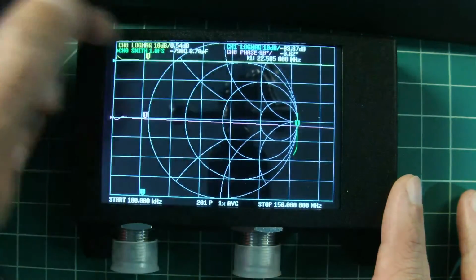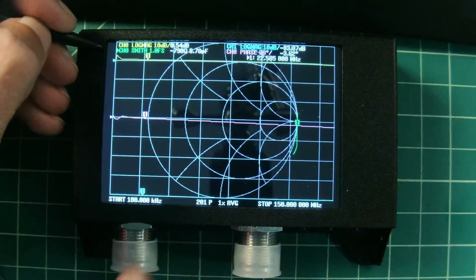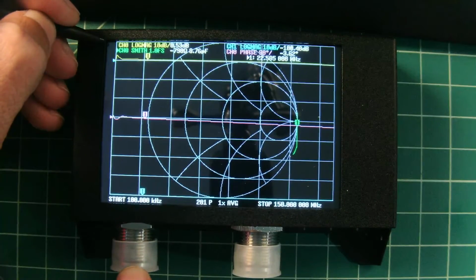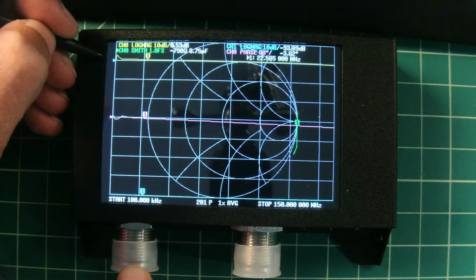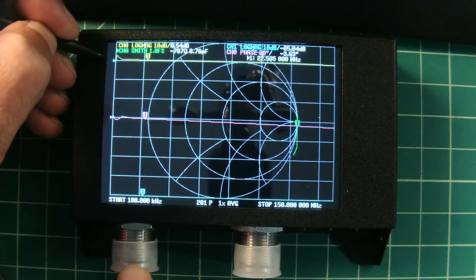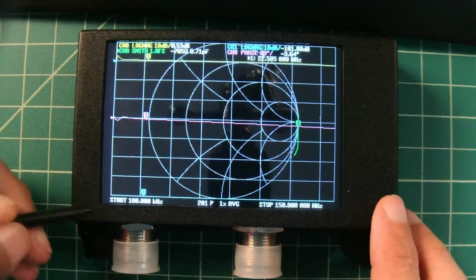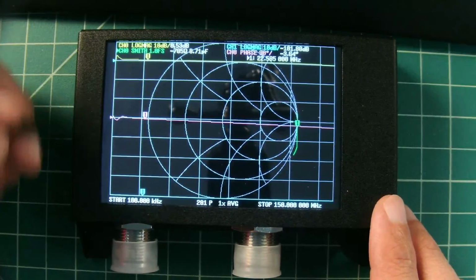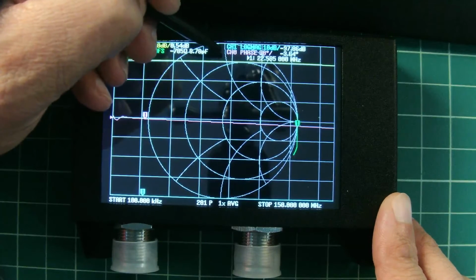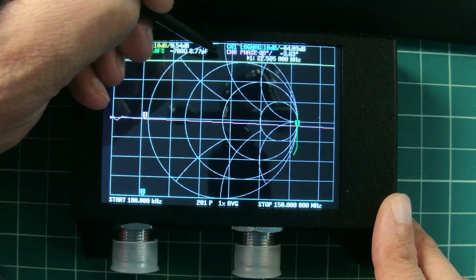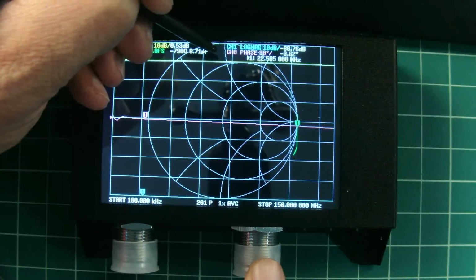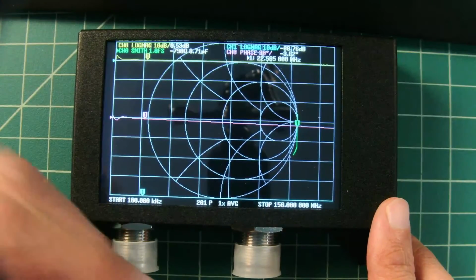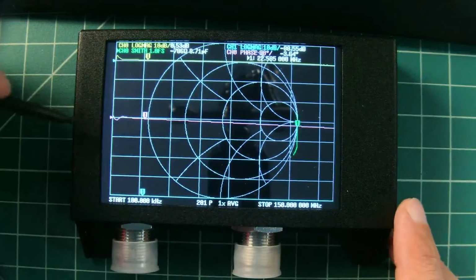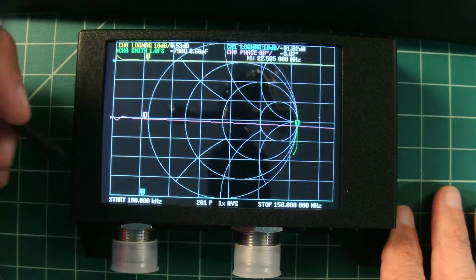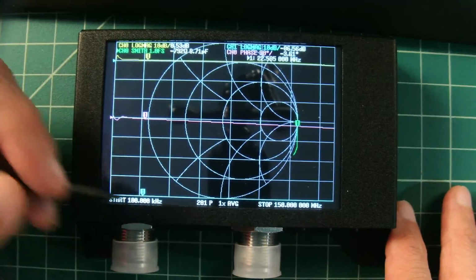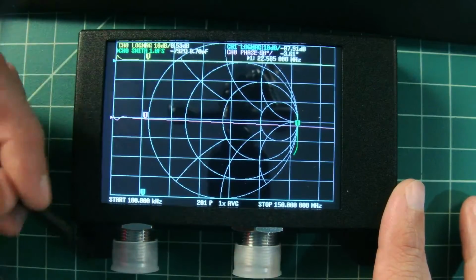When you look at this, your default traces here on channel 0, which is here, we have a log magnitude reflection, which would show us return loss. Our green trace, which is actually trace number 2, is on channel 0, and that is a Smith chart, and that is going to be a complex impedance reflection back. Now I can change these like I just showed you. Our blue trace, trace 1 I believe, is on channel 1 right here. This is a log magnitude trace where we have a signal come out of here, go into here, and then we can measure gain or insertion loss. So that is what we are going to do today. We are going to do some through measurements. And then our last one is a channel 0 phase.